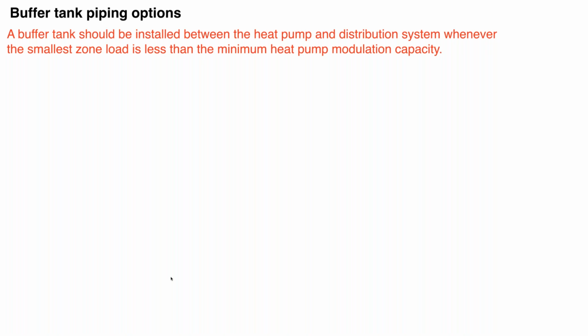But we have minimums on the heat pumps. We can talk about that later on. But let's say, again, we had a nominal 4-ton heat pump, and we have one of these, what I call micro loads. It could be a small towel warmer or a panel radiator in a room. It's a very small heat requirement relative to even the minimum modulation of the heat pump, okay?